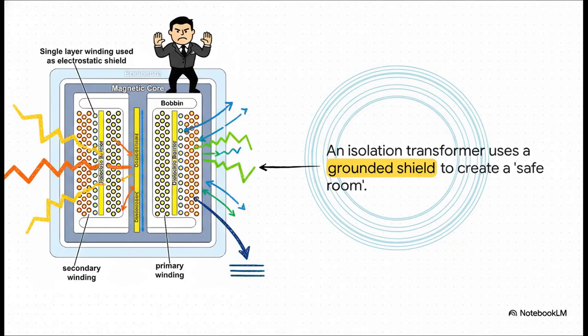This right here is a brilliant example of one of those principles in action. This is an isolation transformer. See that grounded electrostatic shield in the middle? It basically acts like a bouncer at a club. A high-frequency surge comes in, sees that shield as a super easy path to ground, and gets diverted away before it can ever cross over to the protected side. It's like creating an electrical safe room for your gear.